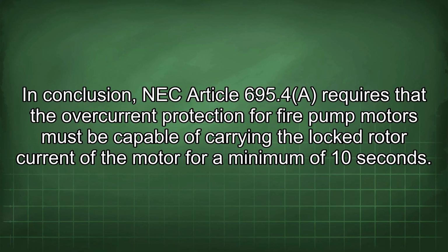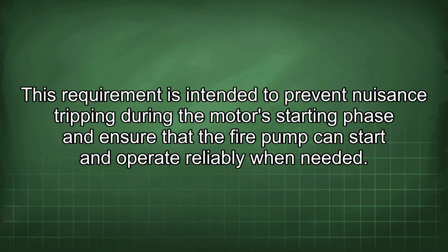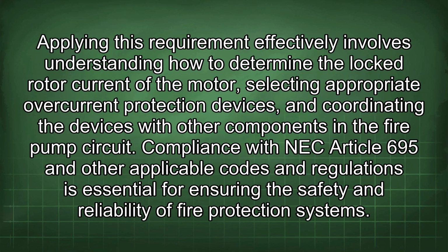In conclusion, NEC Article 695.4 requires that the overcurrent protection for fire pump motors must be capable of carrying the locked rotor current of the motor for a minimum of 10 seconds. This requirement is intended to prevent nuisance tripping during the motor's starting phase and ensure that the fire pump can start and operate reliably when needed. Applying this requirement effectively involves understanding how to determine the locked rotor current of the motor, selecting appropriate overcurrent protection devices, and coordinating the devices with other components in the fire pump circuit. Compliance with NEC Article 695 and other applicable codes and regulations is essential for ensuring the safety and reliability of fire protection systems.